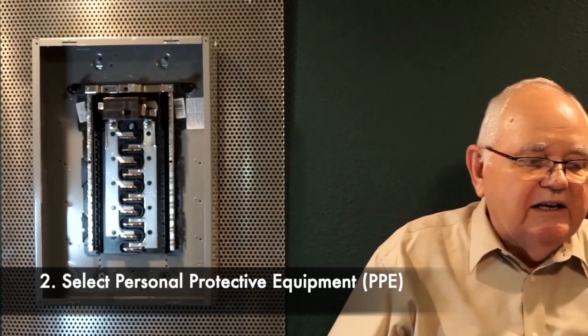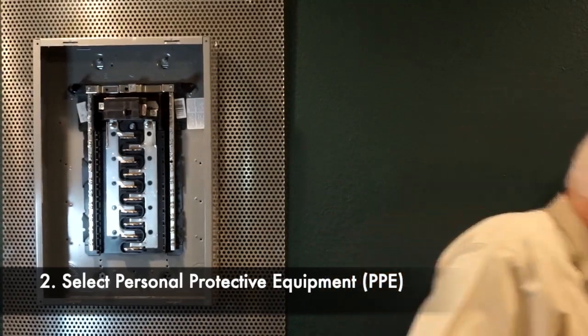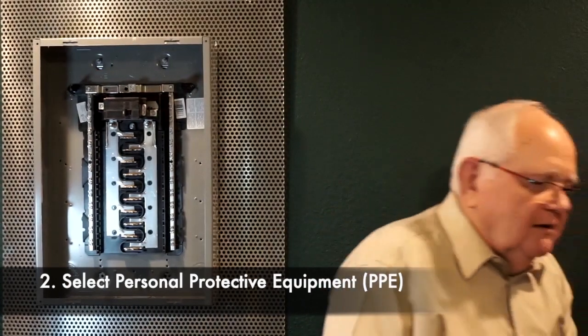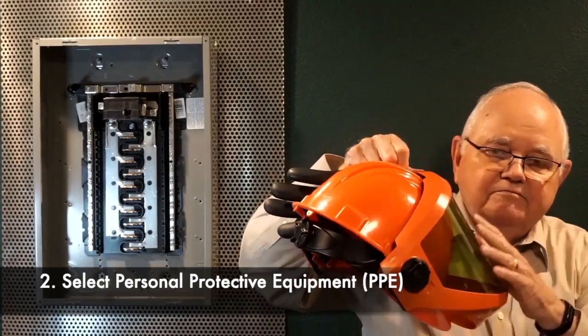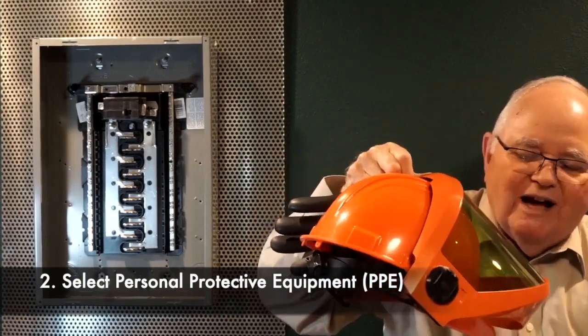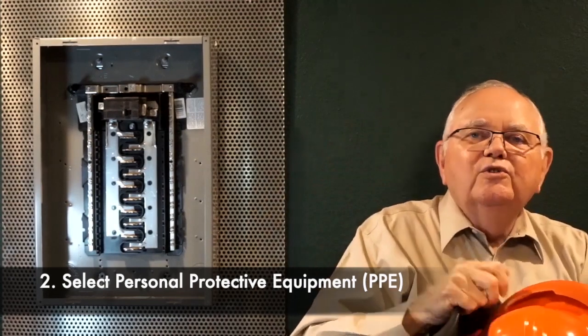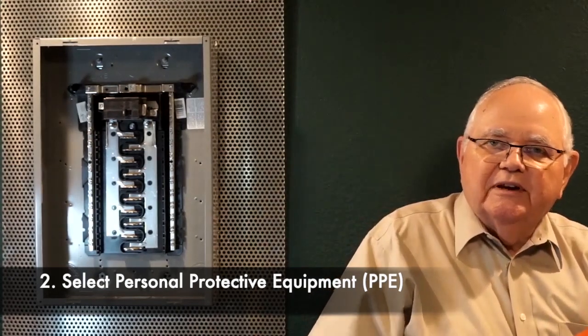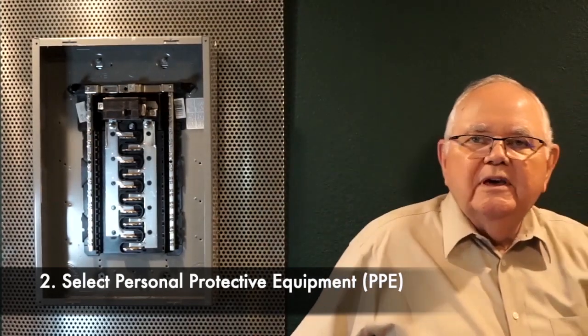The next thing that you're going to have to do practically is, you do your risk assessment, it's documented. You look at your risk assessment, you go, oh, well, this is the PPE I need. I need this level of rubber gloves. Maybe I need a face shield, okay, with a balaclava and so on and so forth. You determine all of that from your risk assessment. You have to select the appropriate PPE and you have to inspect it and make sure that it's safe to use.